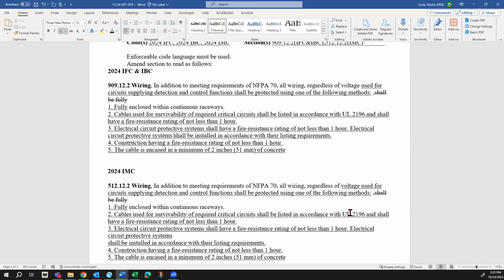And this language is directly out of the 2027 ICC Council's proposal, F139-24. Their reasoning was they wanted the wiring that is part of a fire alarm system, not specifically part of the ventilation control, to have the same protection like a fire pump would. The options basically ensure that those circuits are being protected. Anything specifically related to the fans has to be 2-hour protected by other parts of the code. This is just giving a little more flexibility: as long as the wiring is protected 1 hour, if it's not part of the actual smoke control system, if the system is isolated and designed properly, where the AHJs and the engineers can see that it's engineered properly, then if a smoke detector goes off in one part of the building, it has done its job. It doesn't need to survive 2 hours. Fans need to survive 2 hours. And this was voted on by the ICC Council 13-1.